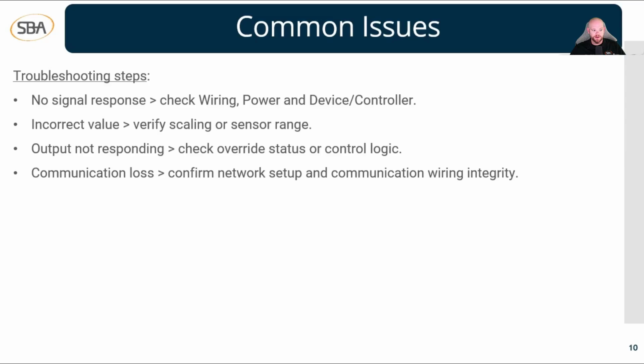Third point here, talking about outputs. We have an output that is not responding to commands. The first thing I would check is the override status in the computer, our software. If it's not responding, but we have it running from program logic, well, if we have it overridden in the BAS, the program logic isn't going to be able to work it. So we have to make sure that the override is off, make sure it's not overridden on or off, and then check the control logic, okay?